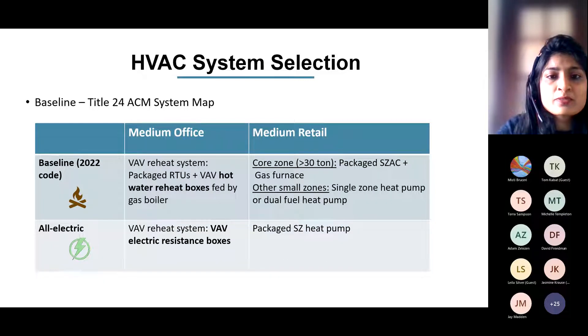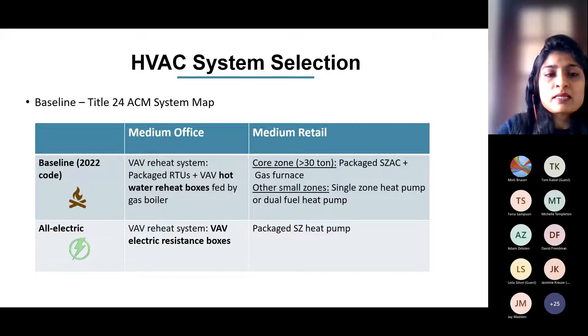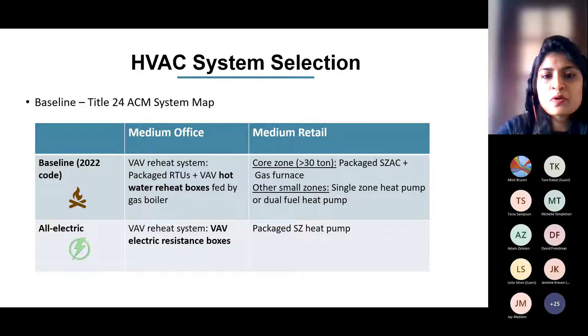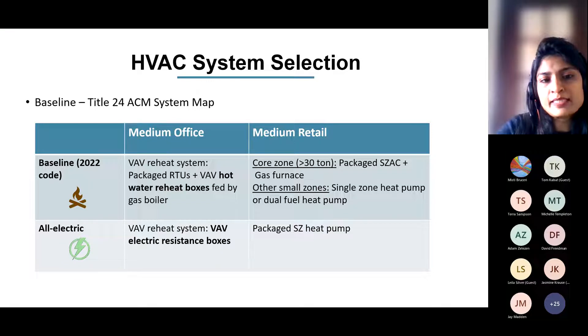There was a question about why electric resistance versus heat pump for all-electric medium office. The more practical system would actually be a central heat pump boiler, but because of modeling limitations — CBECC currently does not have the capability to model a central heat pump boiler system — we are using VAV electric resistance boxes as a placeholder until we have that capability.